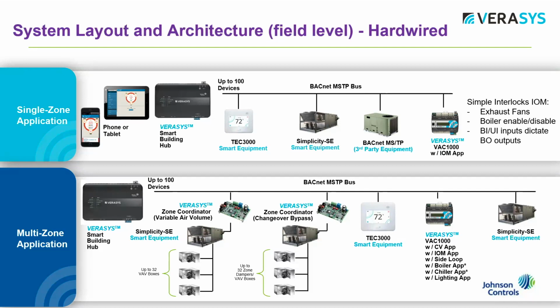And if you're familiar with our other upper end lines of controls, you have not seen zone coordinators previously. The zone coordinator handles the communication between the rooftop unit and the VAV boxes. It's also where the schedule resides, and it's also where some of our trend sampling lives as well. It's used to recognize, for example, requests for conditioned air after hours or on weekends, so you can override the system if an individual comes in and needs conditioned air after hours.